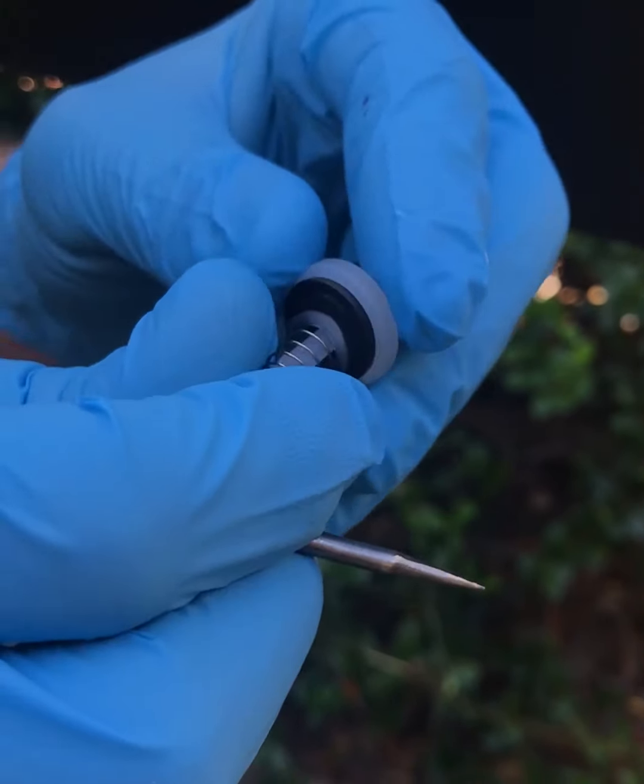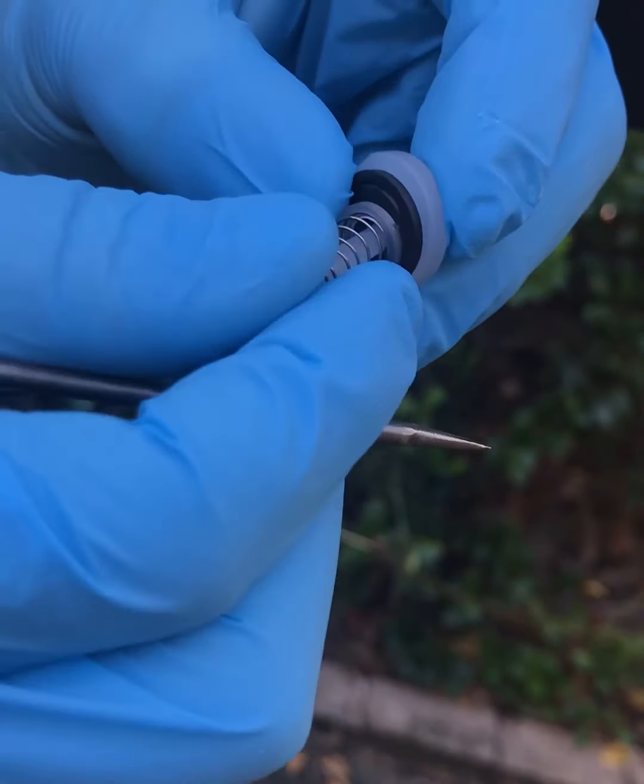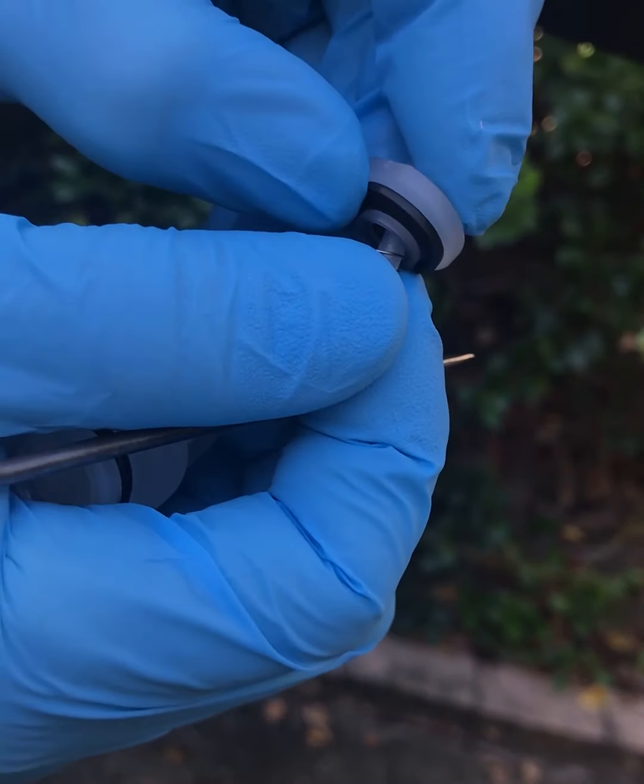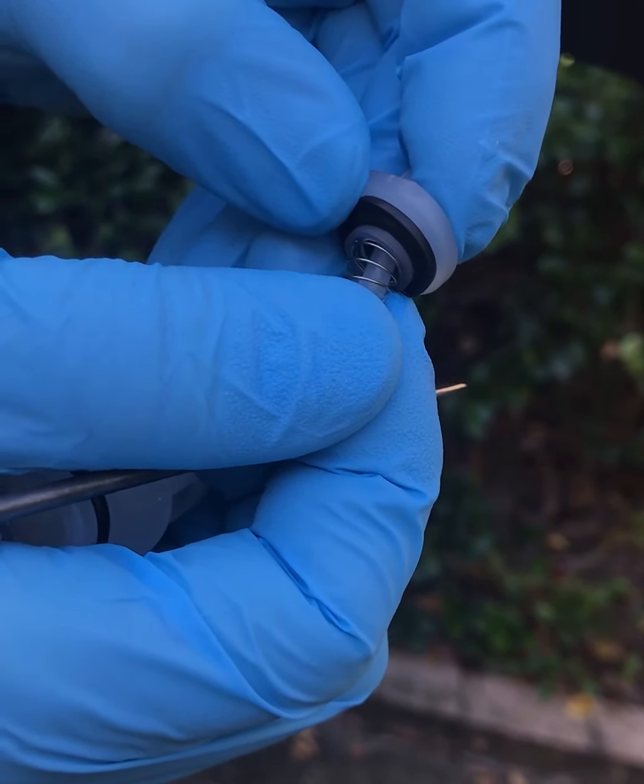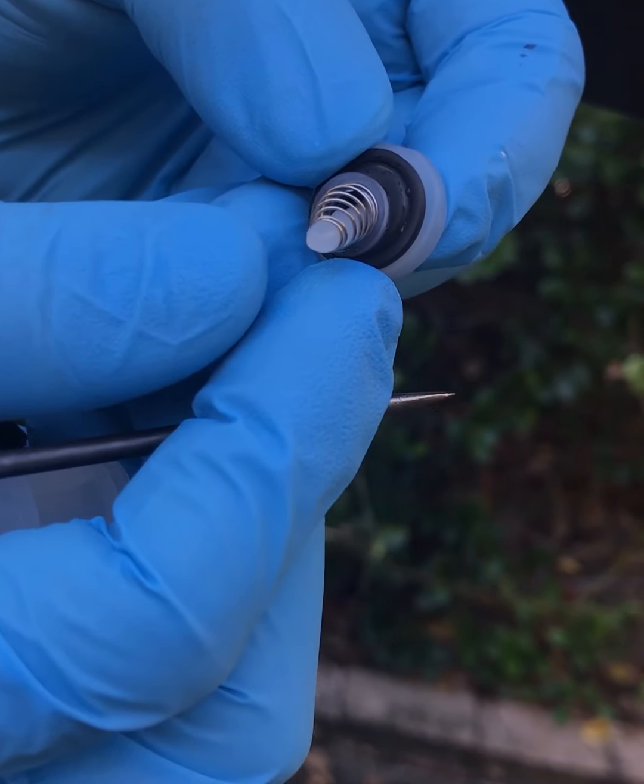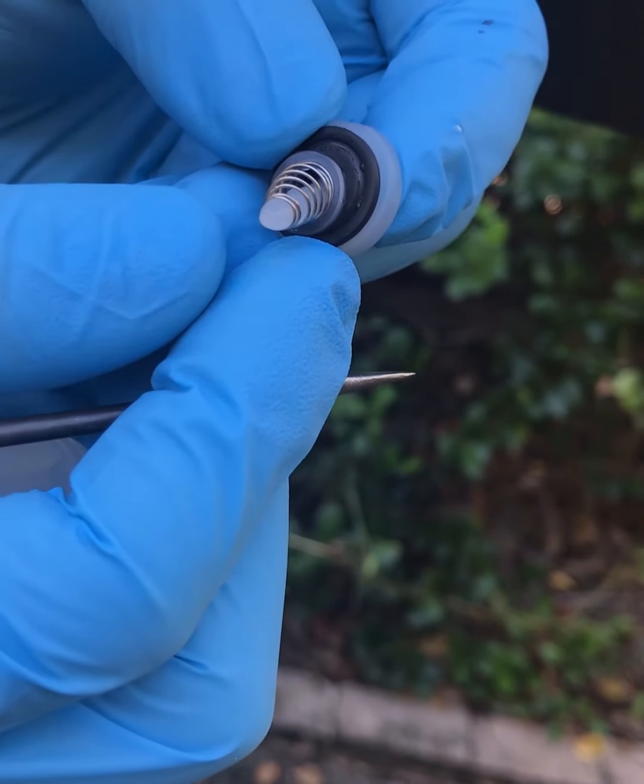And you'll also want to check on the backside of the seal between the spring for any foreign debris or particles. Once the check valve has been thoroughly inspected, it is time to reinsert it onto the bottom piece.